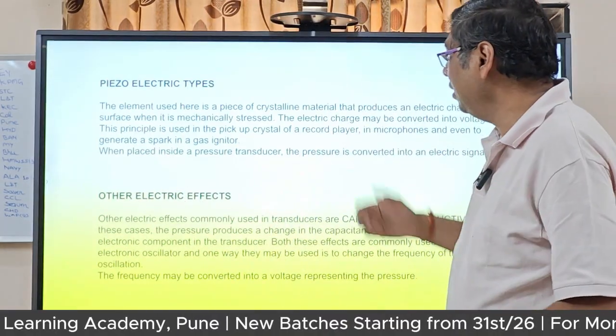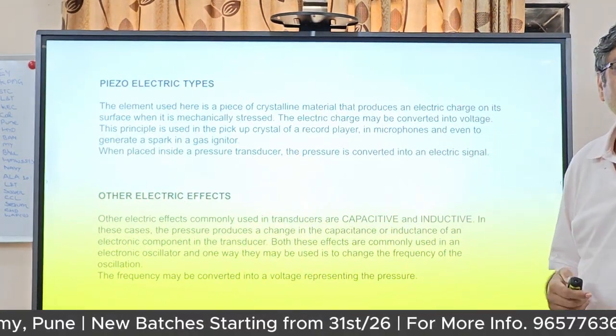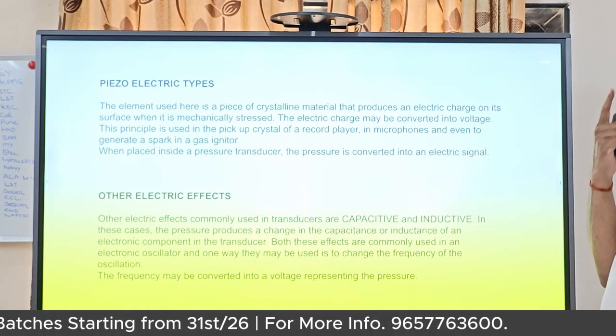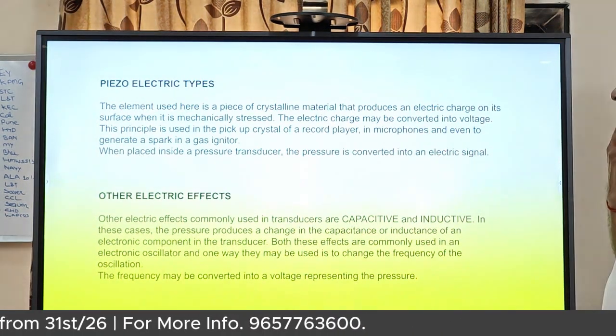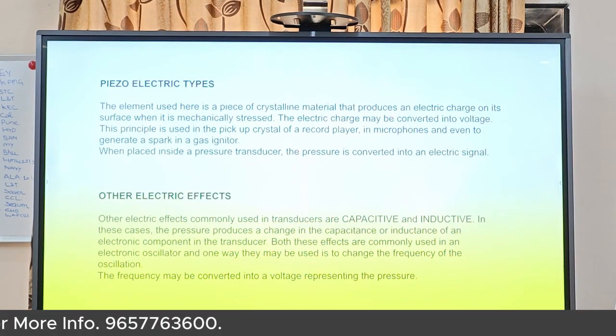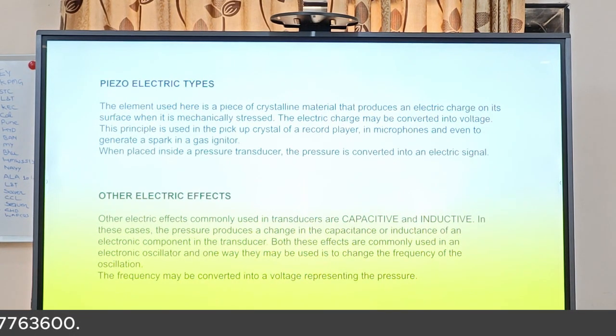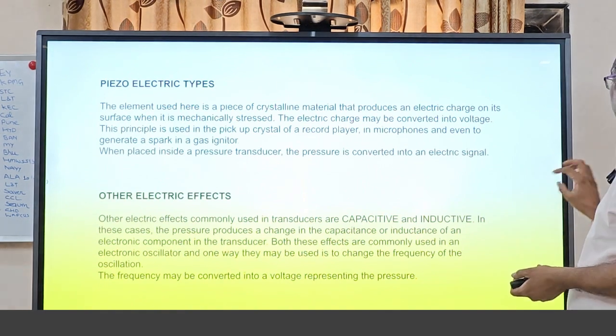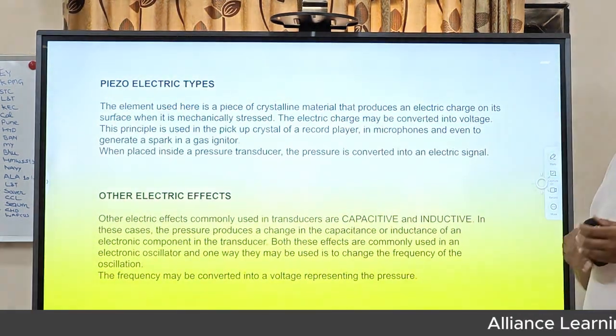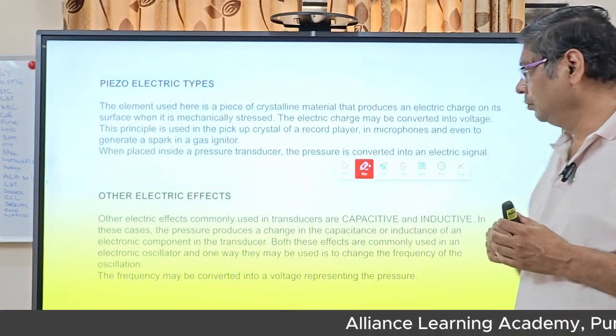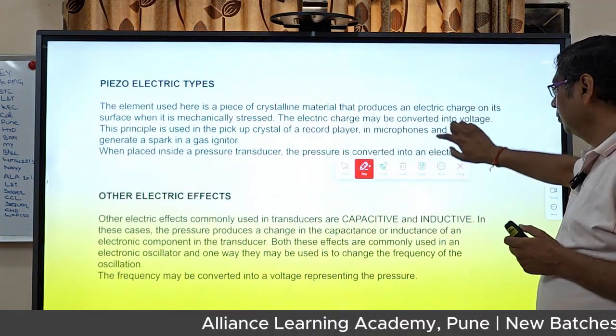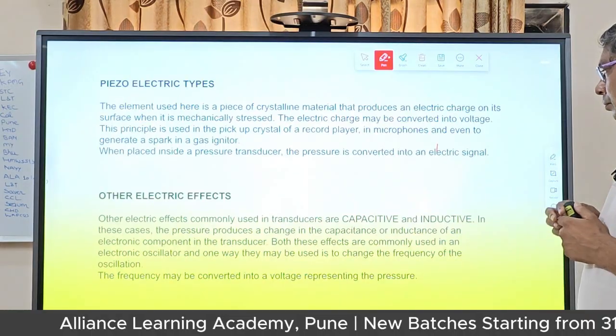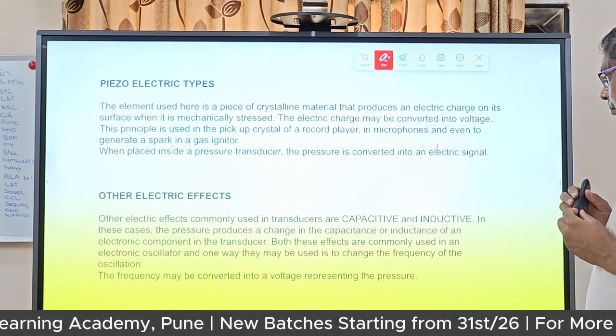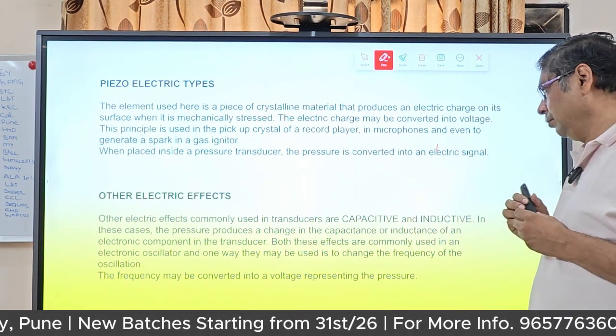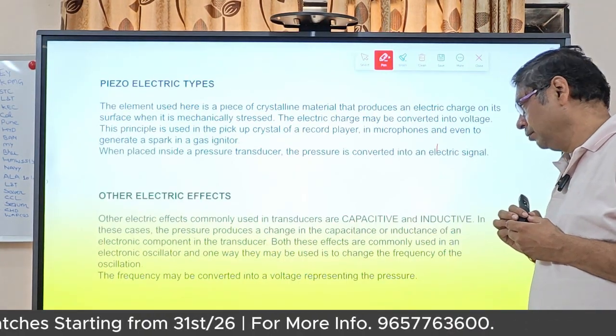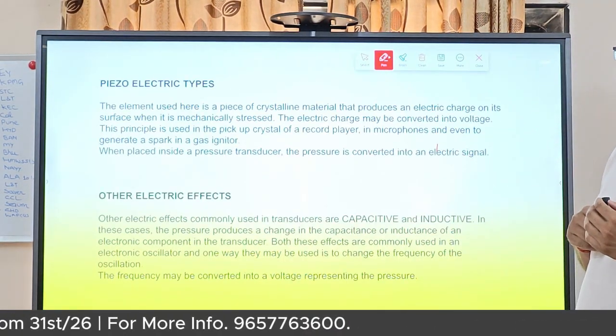Got it? Then other effects - read loudly. Other electric effects commonly used in transducers are capacitive and inductive. In this case, the pressure produces a change in the capacitance or inductance of an electronic component in the transducer. Both these effects are commonly used in electronic oscillators, and one way they may be used is to change the frequency of the oscillation. The frequency may be converted into a voltage representing the pressure.